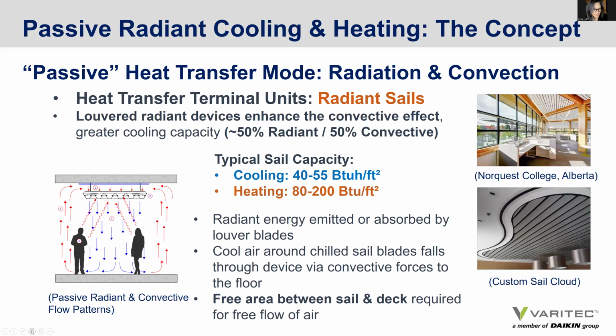A radiant panel system, however, can be a ceiling system. The manufacturer we represent could provide active and inactive panels within their ceiling systems, so you have a seamless integration so that you have tighter control and a better aesthetic effect, perhaps, in a panel if that's what the architect is looking for. Radiant sails do, however, offer a very dynamic linear quality in the open ceiling application, and you can see these devices can be customized to meet the aesthetic design desires of an architect in a building very effectively.